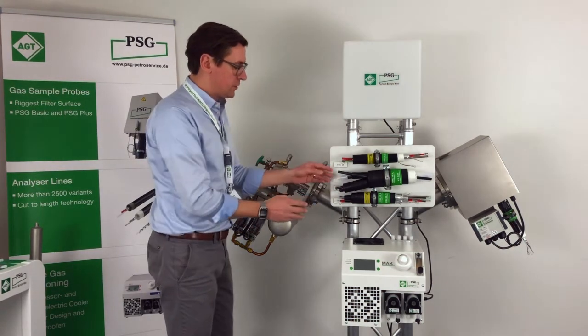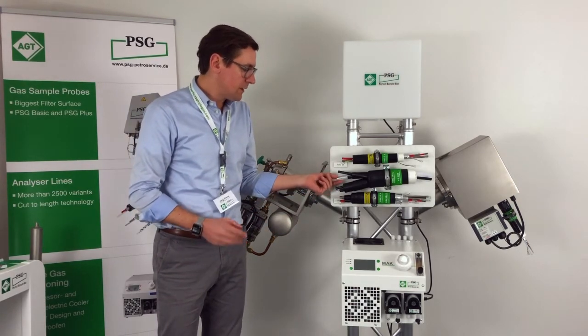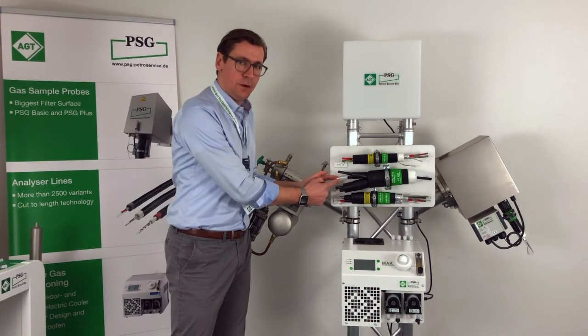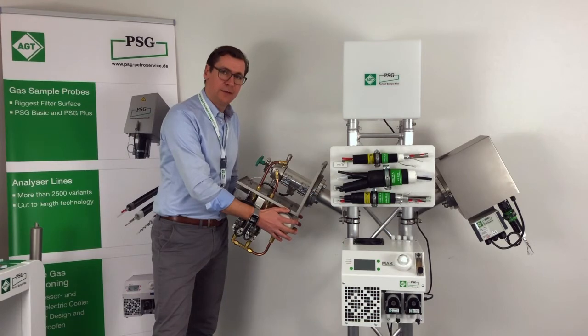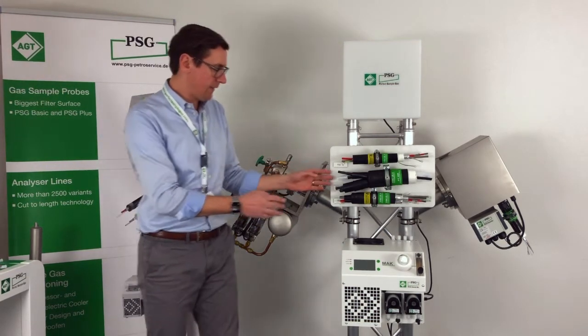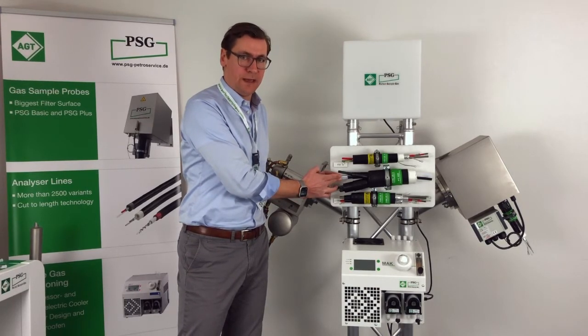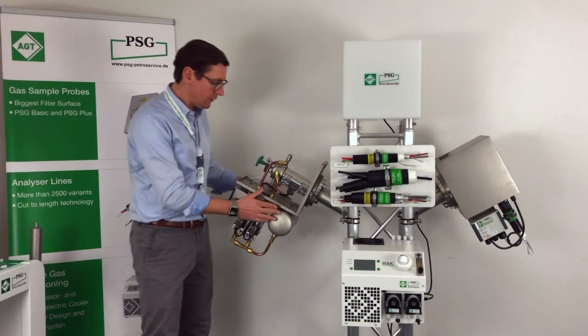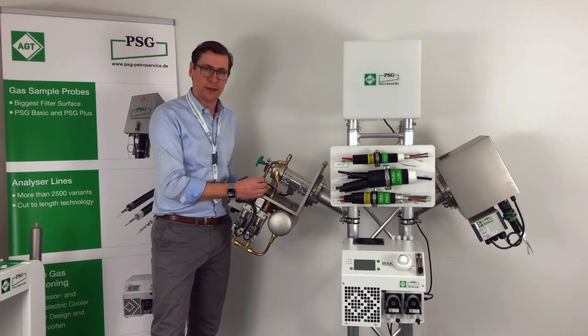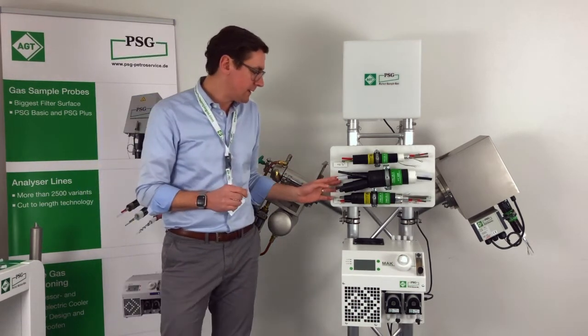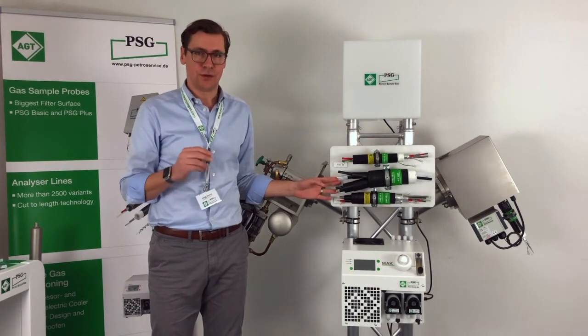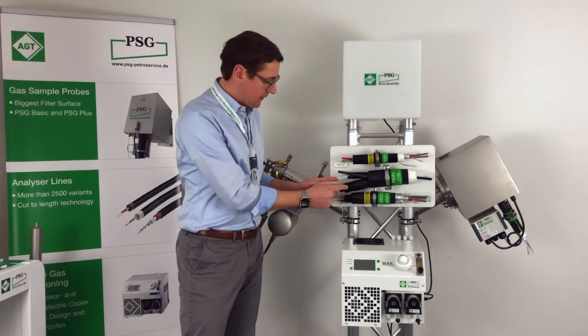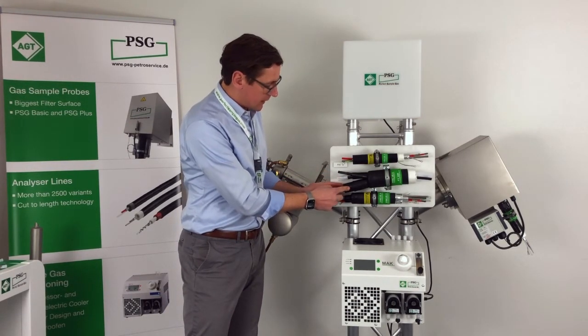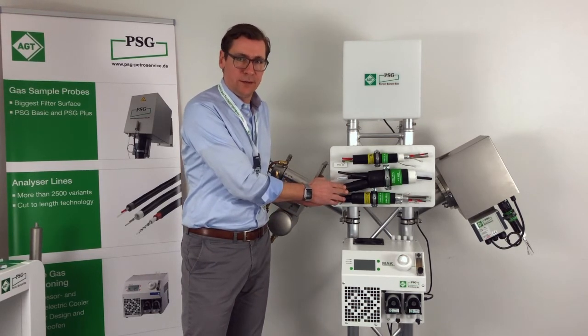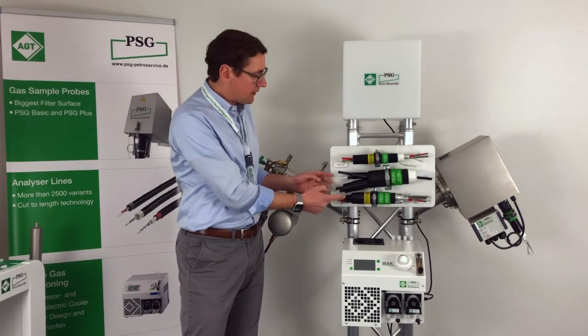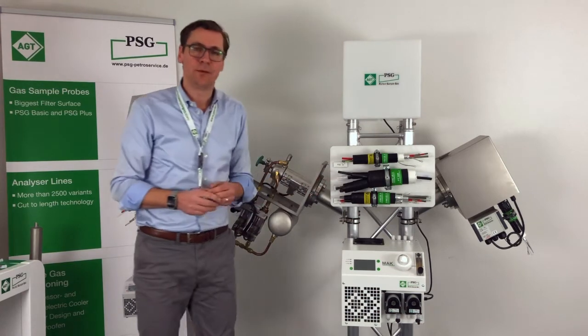What we do with the PSG Hybrid Line is we use the volume of the PTFE tube in order to avoid an accumulator like this. As soon as you have a length of, let's say, from 25 meters, you will have enough volume to supply the back purging. Another very big advantage is that we have two different temperature zones inside the PSG Hybrid Line. There is the first zone, which is heated up to 180-200 degrees C for the gas sample itself, and also the back purging is heated up to 100 degrees C.